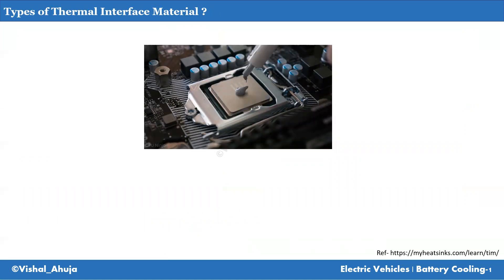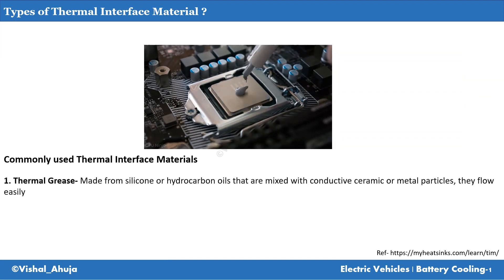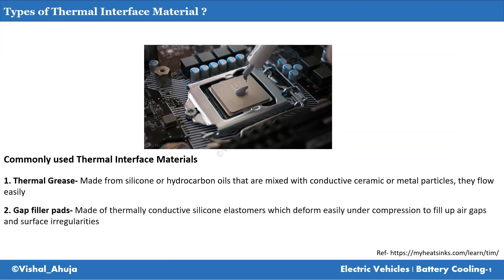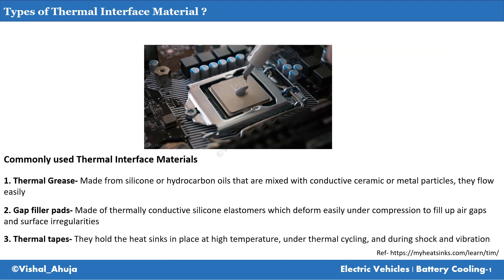What are the different kinds of interface materials available in the market? The first is thermal grease, which you might have seen applied on top of a CPU before attaching to the heat sink. It is made of silicon or hydrocarbon oils mixed with conductive ceramic or metal particles. It flows very easily to fill the irregularities and gaps. The second most popular is gap filler pads, made of silicone elastomers which deform easily under compression to fill air gaps and also absorb some vibrations in the system. Third is thermal tapes, which provide adhesion force between two joining surfaces and prevent relative movement.